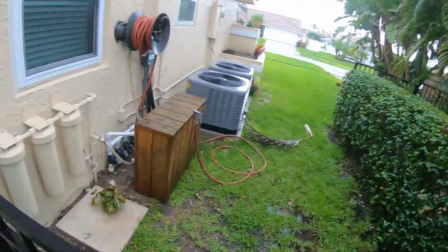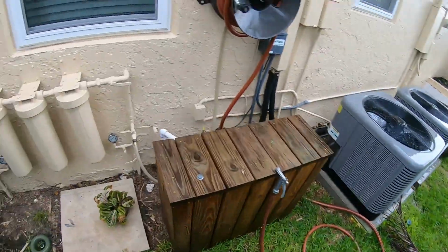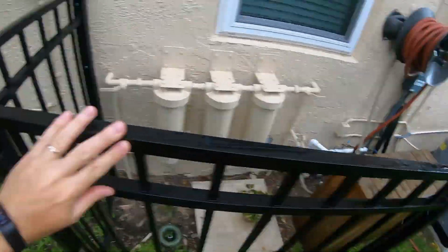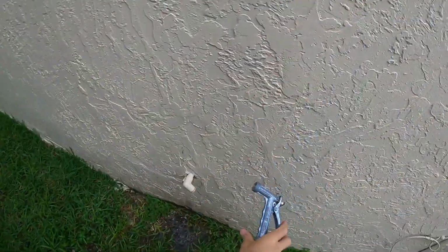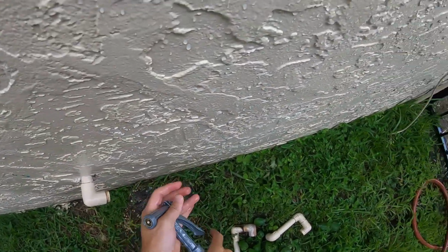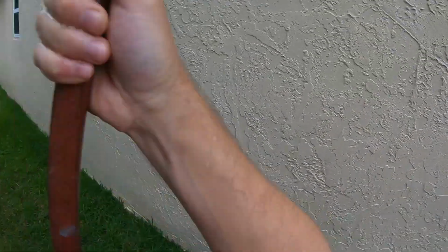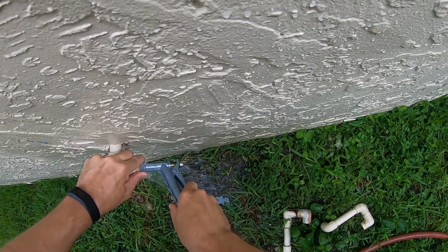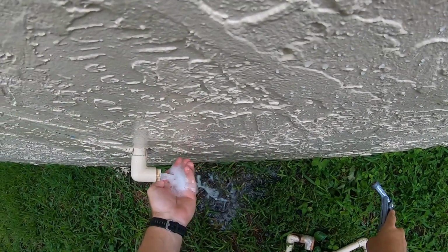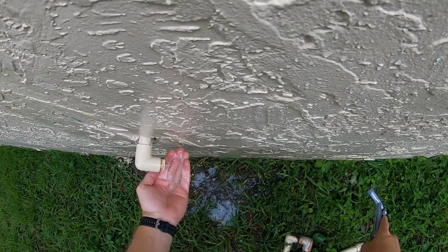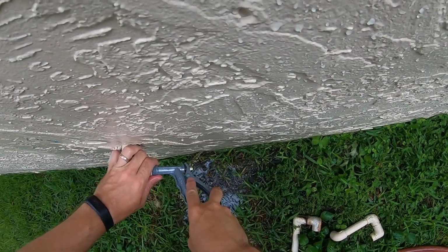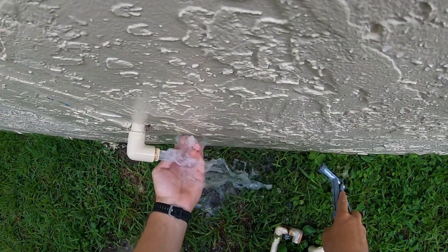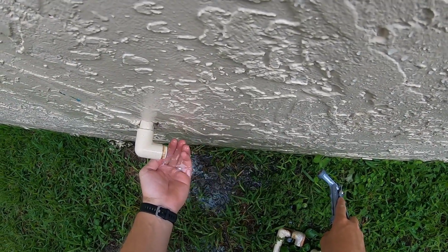Now, before I talked about the garden hose, and this one you have to be very, very careful with because again, you don't want to overload those pans because they will overflow and then you'll have the same problem you're trying to avoid. So what I typically do is I'll hook up the garden hose like this after I untwist it and just do short bursts. So we'll go like no more than a couple of seconds. And if things are really dirty, you'll see crap start to come out. A short burst. Just like that.